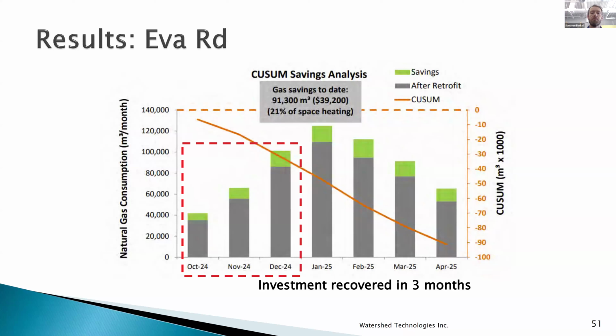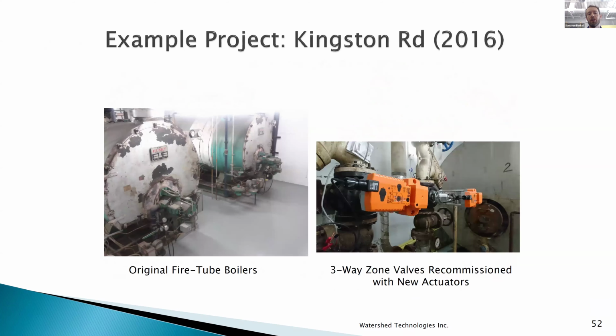And just in the first 3 months, they recovered that initial investment of $13,000. So a very profitable project. This is another project we did in 2016. I wanted to show an example of an older project just to illustrate the savings, the longevity of the savings. So this was a really old boiler plant with original fire tube boilers. Part of what we did was recommission the zone valves for the building as well, new actuators.